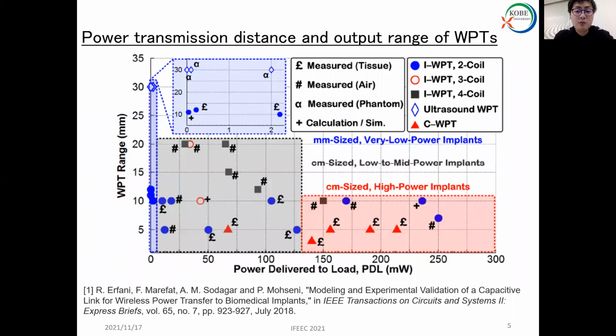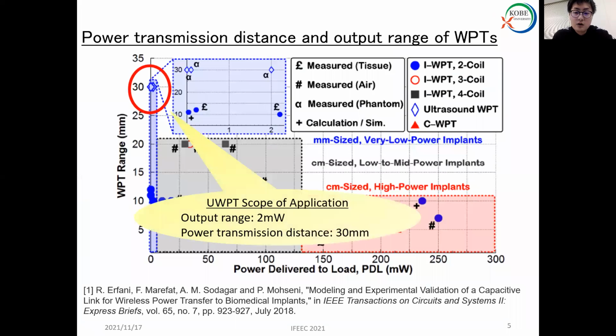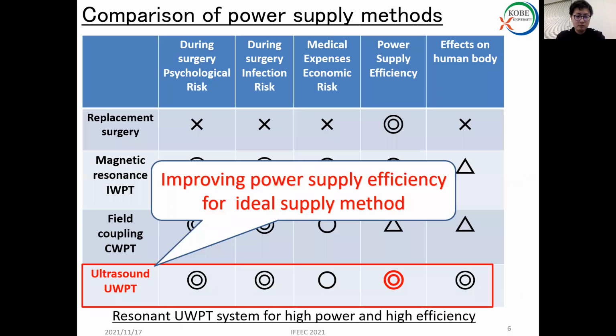This figure shows a comparison of power transmission distance and output range of each WPT method. The IWPT and CWPT methods are capable of outputting power over a wide range and relatively short distance. This is the method used for industrial application. On the other hand, UWPT has the advantage of a longer power transmission distance than other methods, but due to sound attenuation caused by obstacles such as skeletons, the power range is generally low, and the power transmission efficiency is low. Because of this, the current application of UWPT is quite limited. In this study, we propose a resonant UWPT system that incorporates a new resonant tank as a countermeasure. A goal of this research is to increase the output power and efficiency of the system and to expand the application of UWPT.